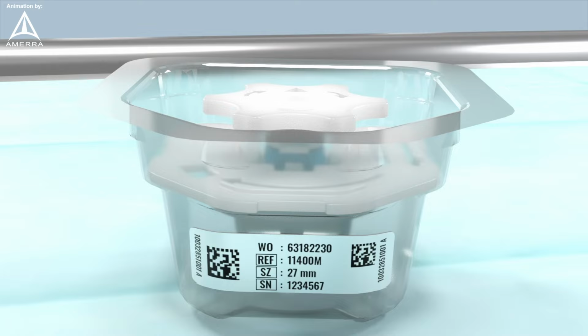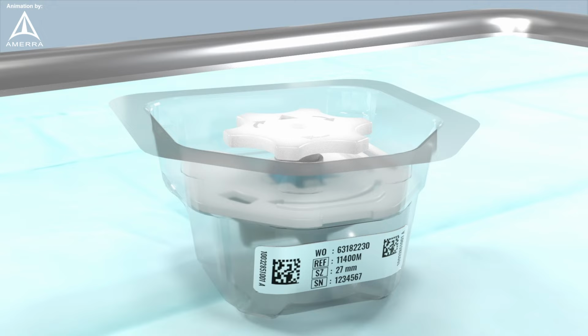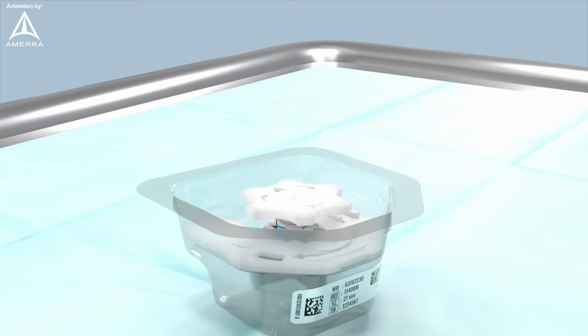to Edwards Lifesciences. Please note that due to the dry storage feature of the Resilia tissue, the mitral valve does not require soaking. If the valve is rinsed prior to implantation, it must then be kept hydrated with sterile physiological saline irrigation on both sides of the leaflet tissue throughout the remainder of the surgical procedure. Rinsing every 1 to 2 minutes is recommended.